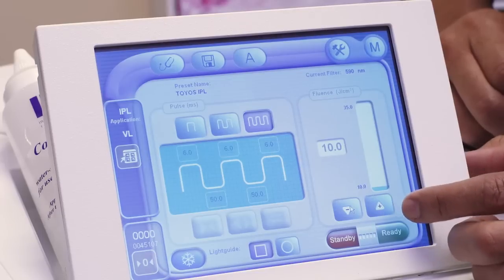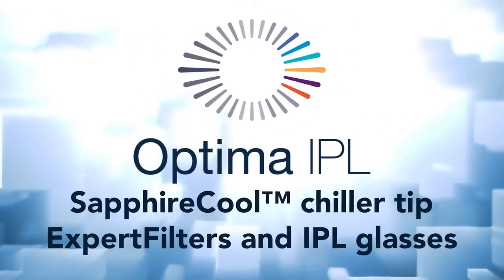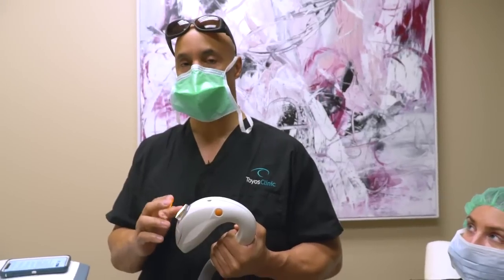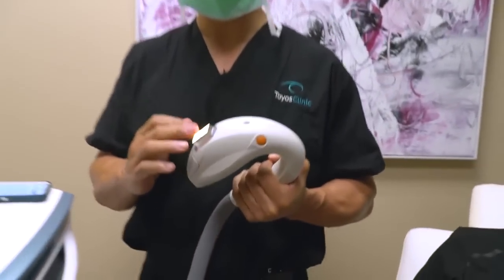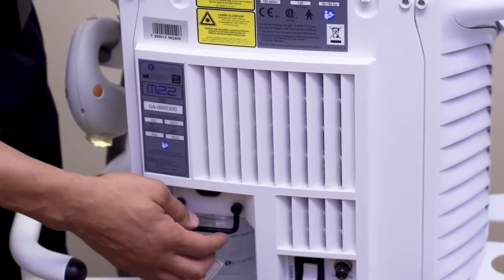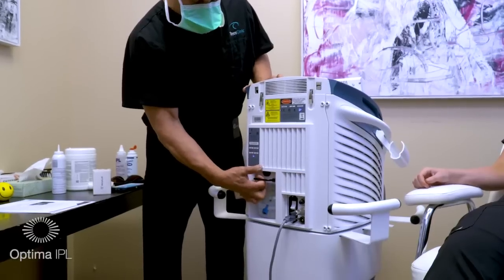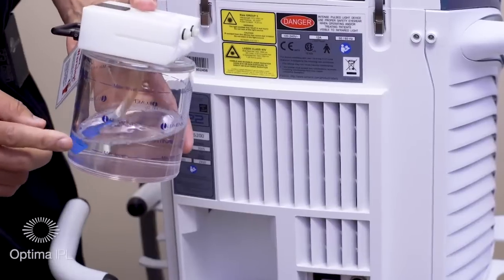These are the parameters we're going to use for a dry eye treatment. The Optima IPL actually has a chiller plate — distilled water is going through here, chilled so the foot plate isn't hot when you're doing treatments and you're not burning the epidermis. In the back here is where you have the distilled water feeding into the chiller plate. You always want to make sure the water is full — I usually keep it above the fill line.